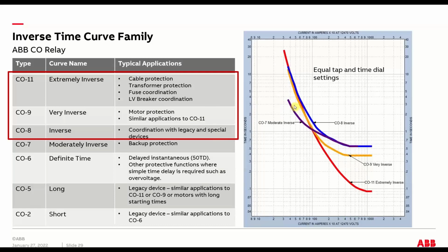Here's the curve family that's pretty typical for relays. There were all these model numbers dependent upon which manufacturer you had. ABB/Westinghouse called them CO, and then gave them a number at the end. GE was IAC with a number, but then they had terms like extremely inverse, very inverse, inverse, moderately inverse. The terms are sort of what the curve is, but they're not consistent across manufacturers. Now there are some standardized versions of it. So there's an ANSI standard inverse and extremely inverse, but there's also the CO inverse and the IAC inverse, and those are different.